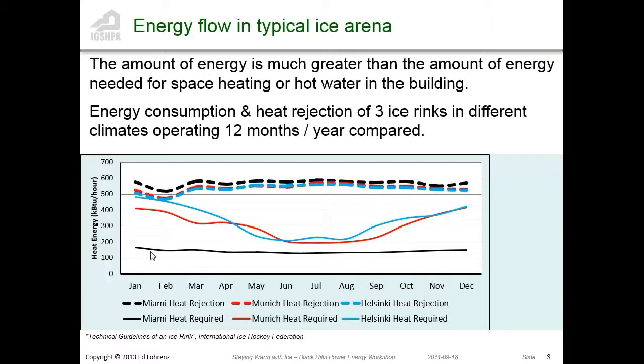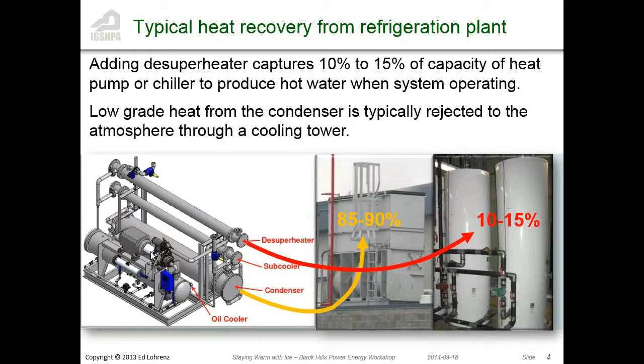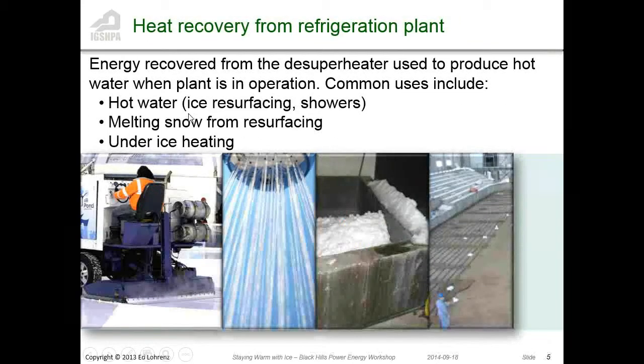And with a typical chiller, sometimes they'll put the equivalent of a desuperheater on these chillers. Maybe 10 to 15% of the capacity can be used to heat the domestic hot water for showers or whatever, and maybe melt a bit of snow that they shave off the ice. But generally it hasn't been used very much in the past. Whatever they use it for, they can use it to flood the ice, for showers, a lot of showers going on in there, and for melting snow that they take off the ice probably once an hour or so.